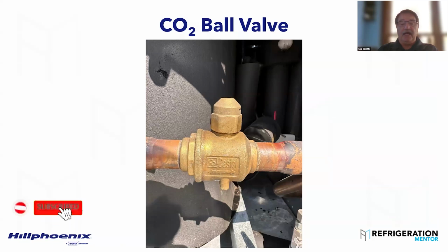So this is one of our new Castel valves. These are an Italian-built valve that we're utilizing in place of the old Sharp valves. And I'm guessing everybody that's worked on one of our old racks had to put a cheater bar on the valve to open or close it. This is a pleasure, trust me. Even when you pump down the vessel, the differential of 400 pounds, it still opens up smoother.